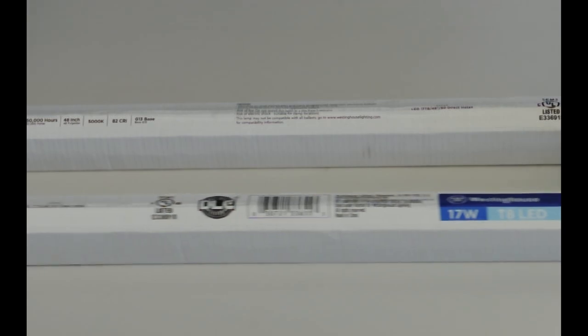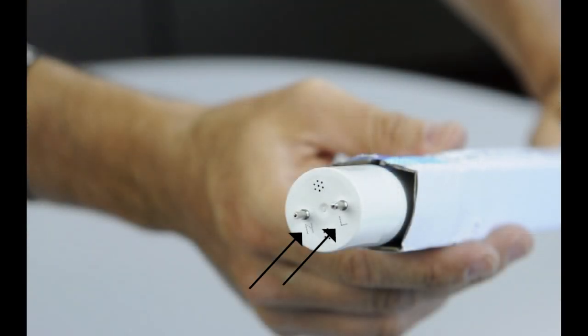Only one end of the TLED tube receives power. The powered end is indicated by mark with L and N on the tube itself.